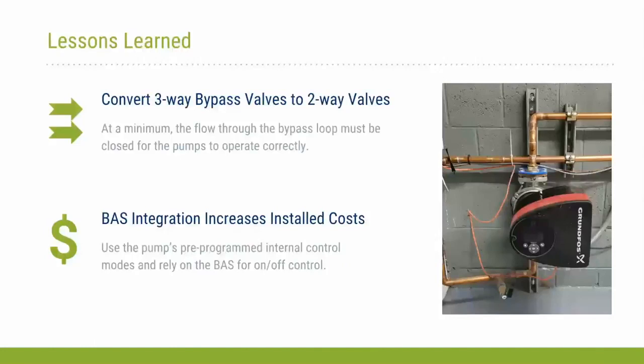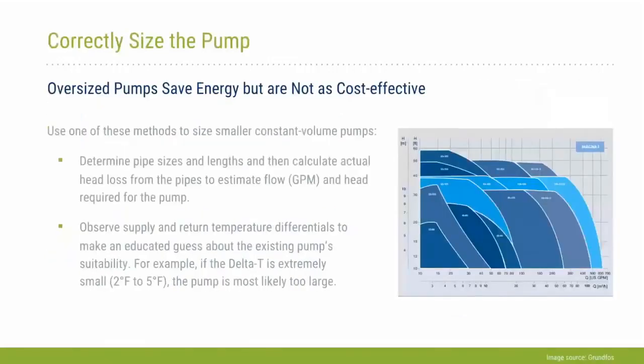So the lessons learned that we have, I think we covered these already. For any heating or chilled water or radiant baseboard application, you do need to make sure that if they have three-way valves, you're either converting them to two-way valves or closing off the bypass so that it's allowed to operate as a variable flow system. And as we noted on the last one, BAS integration costs can greatly increase the overall price to the point where those could be more expensive than the pumps themselves if all the BAS points were integrated. Okay, next slide.